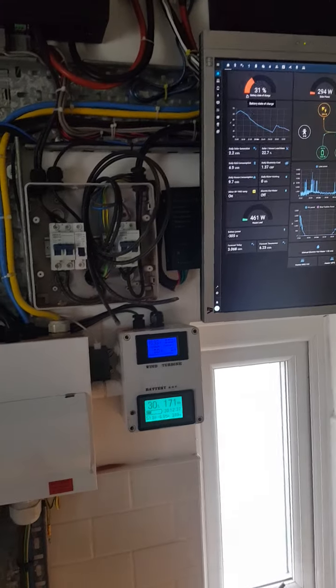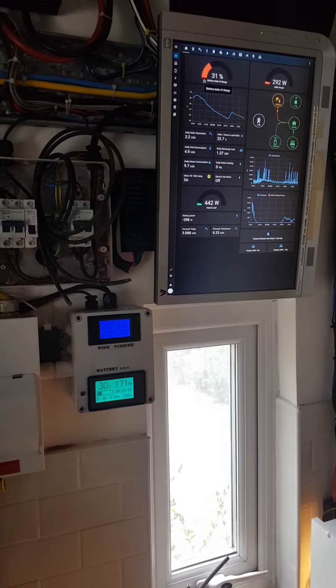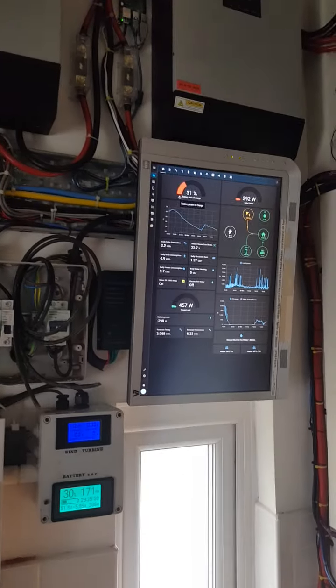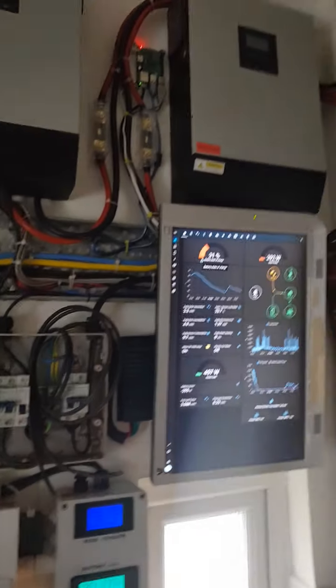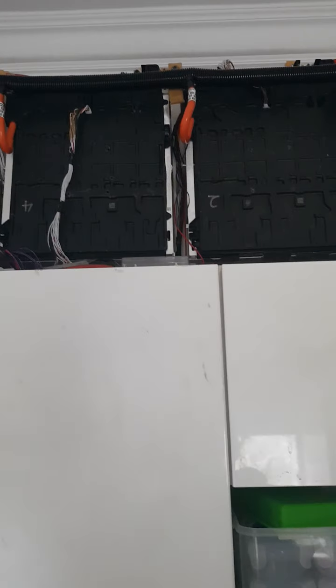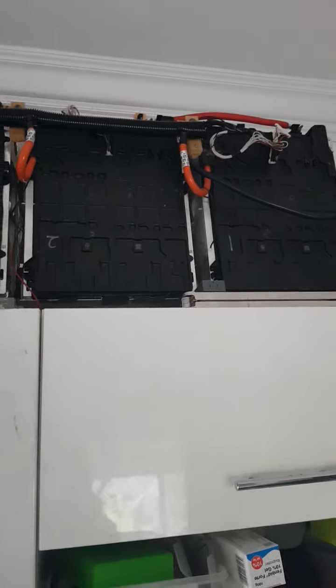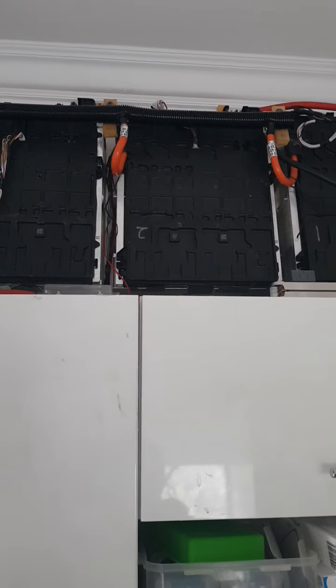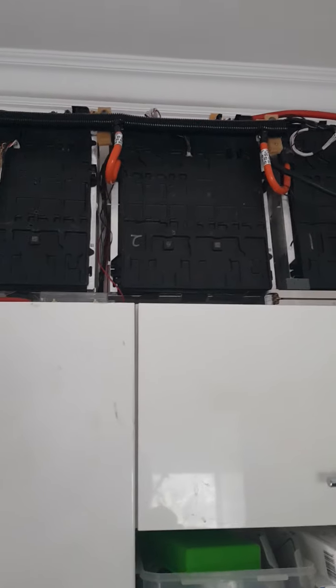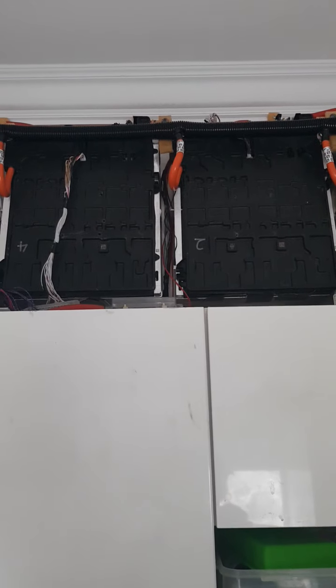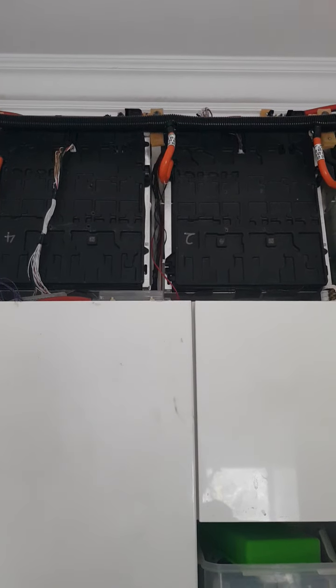So what we mean is you might have 10 kilowatt inverters because by the time you've got your kettle, your cooker, this, that and the other all turned on, you're drawing 10 kilowatts of power. Your batteries, however, you've decided you only need 10 kilowatt hours of storage per day. That's true, however trying to pull 10 kilowatts out of something like that is a lot of amperage, and sometimes it's more than what they can sustain.